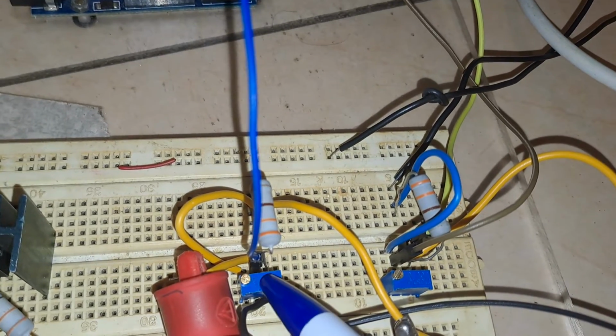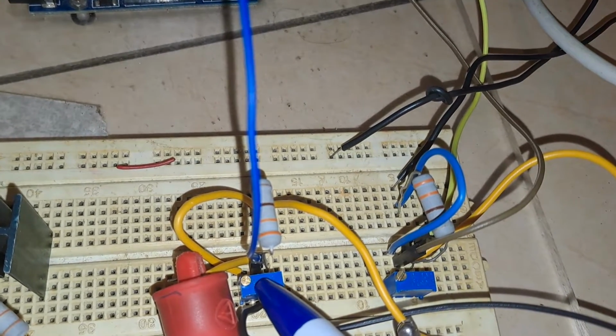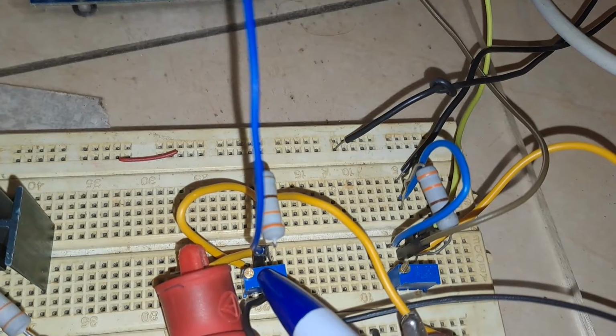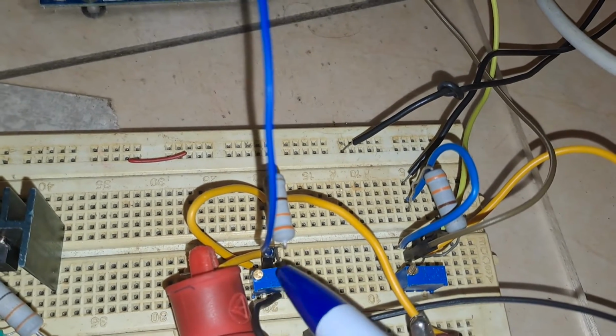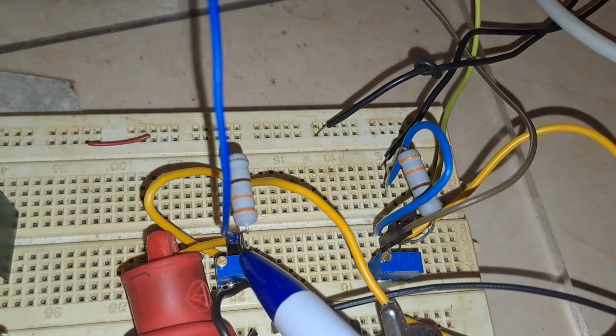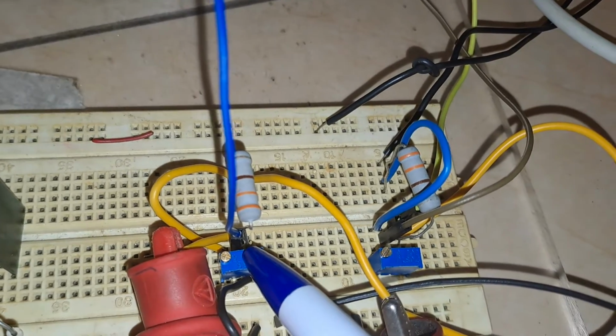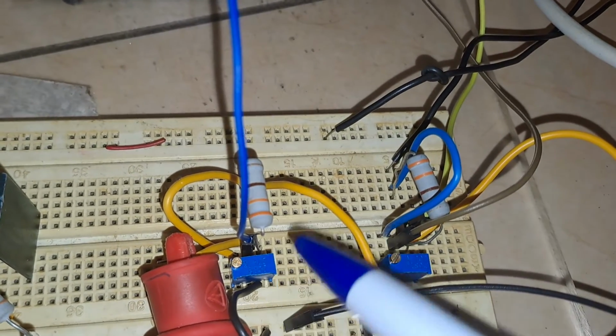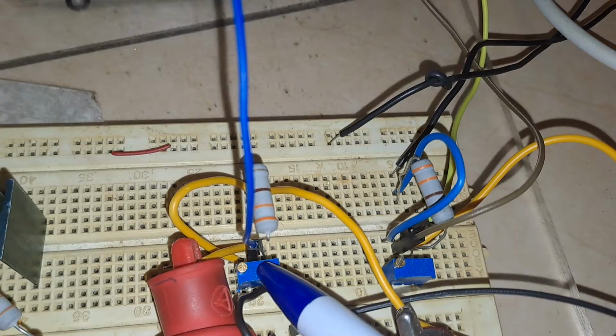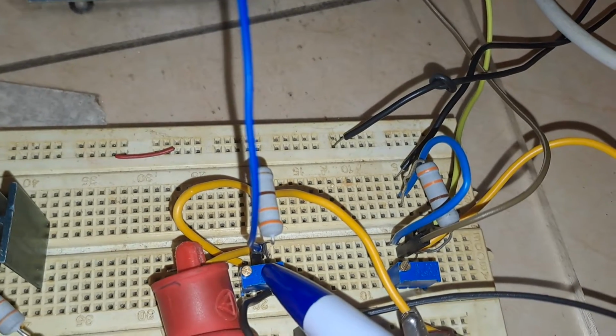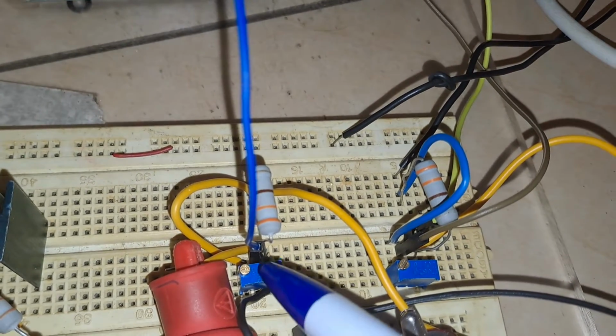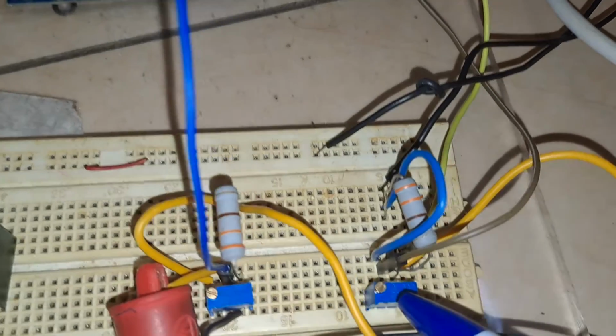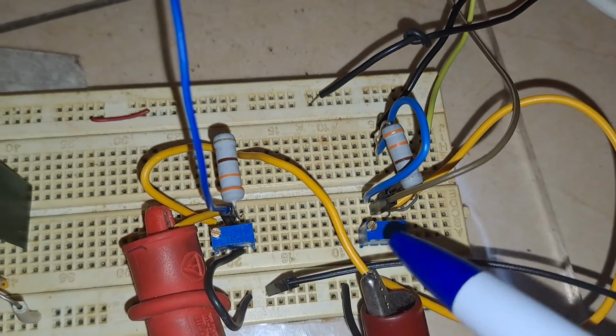So this potentiometer is the single point calibration potentiometer. Either we can adjust the zero or we can adjust the span. Since the graph is a linear graph, we are having resistances here, so we don't need to adjust zero and span. Only single point calibration is sufficient. You can see both the channels have adjustment potentiometers.